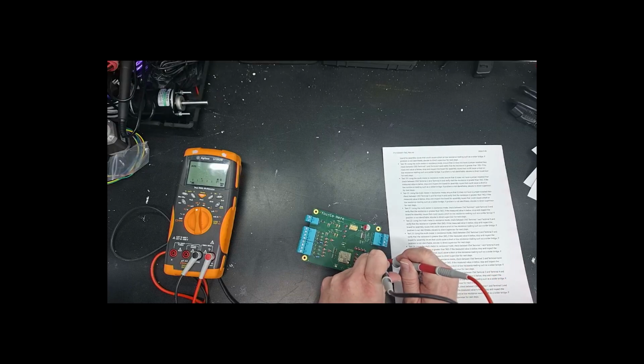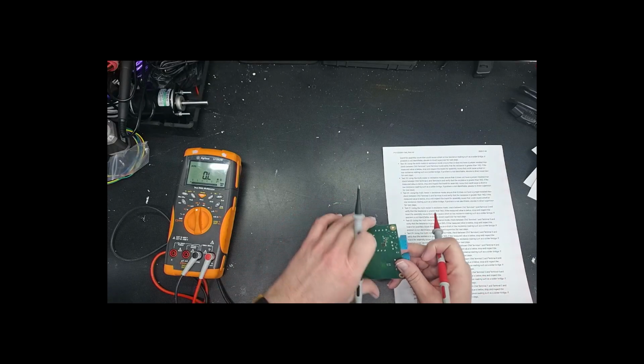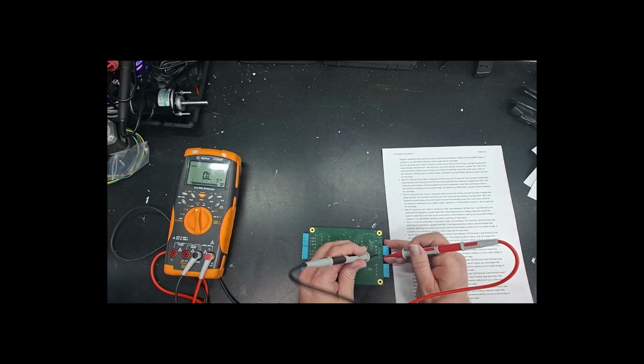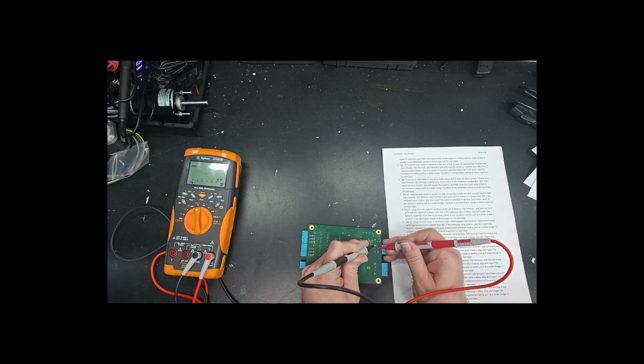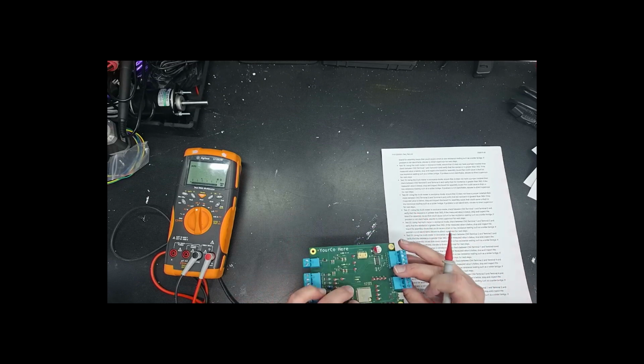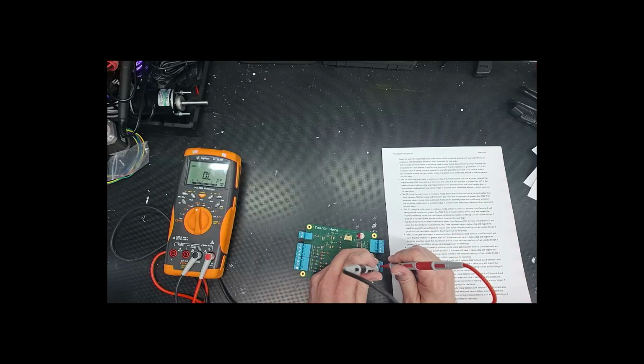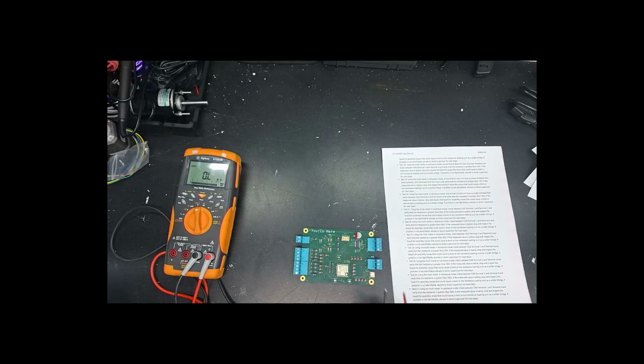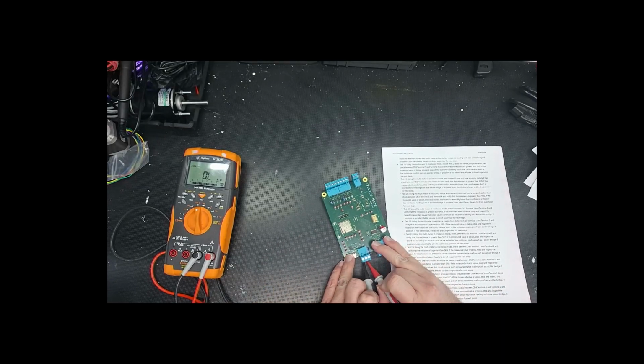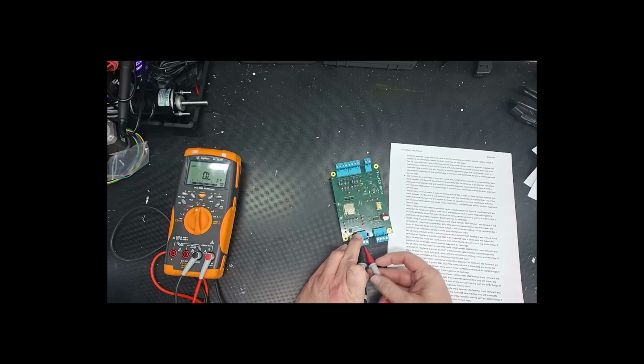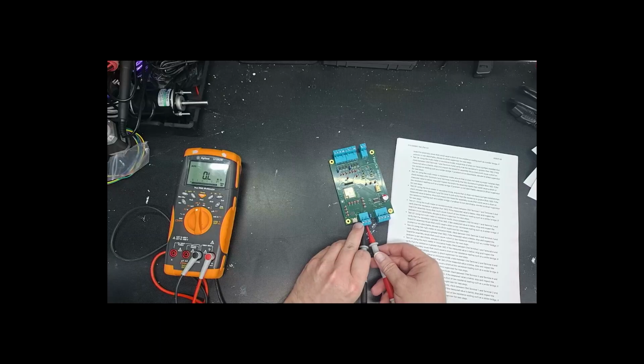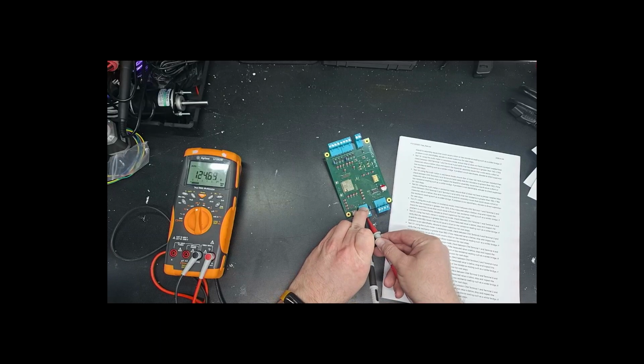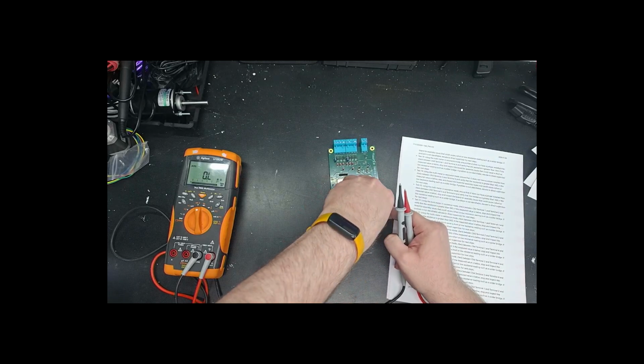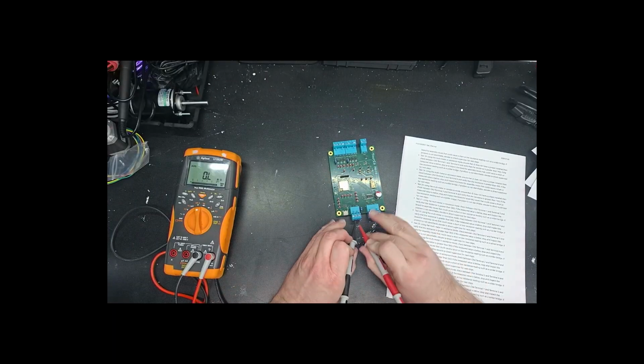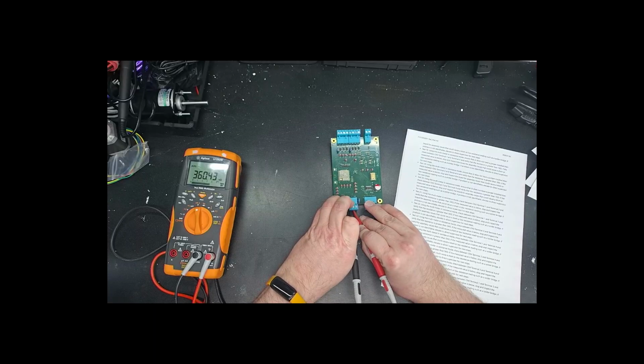So between A and B there should be 120 ohms. Because here's 1, here's 2. Wait a minute. I'm not getting it through the terminals up here. That's not good. Let's make sure I'm getting them down here. Did that actually register? Okay, I'm just not getting them on the terminal screws. They must not be making connection. So that's good. That was one of the tests that I was afraid had failed, but it's fine. It just wasn't picking up on the screws. They must not be making enough contact, and that should be practically open.